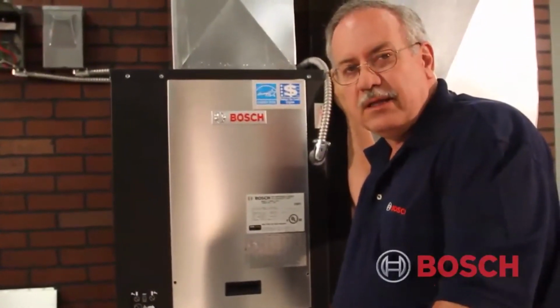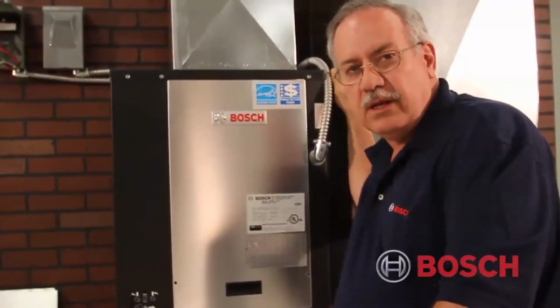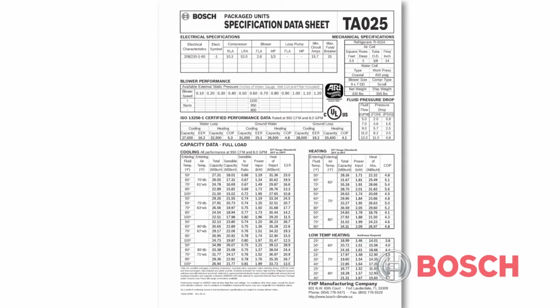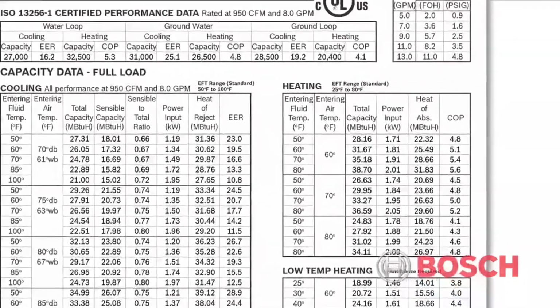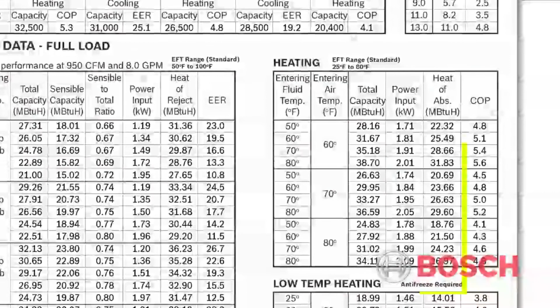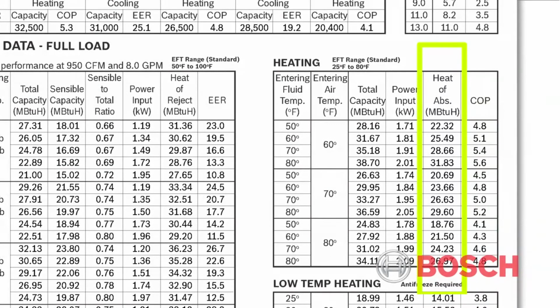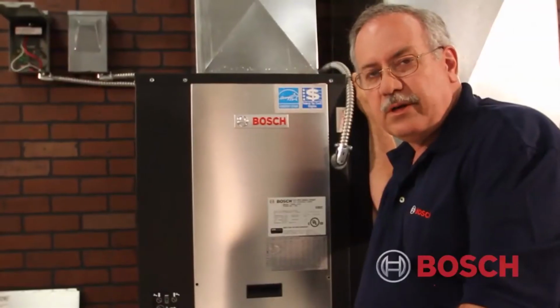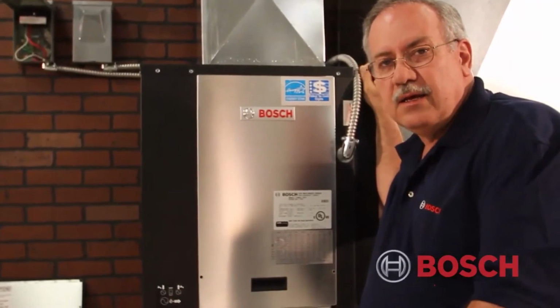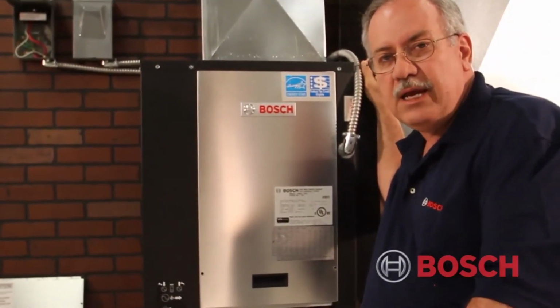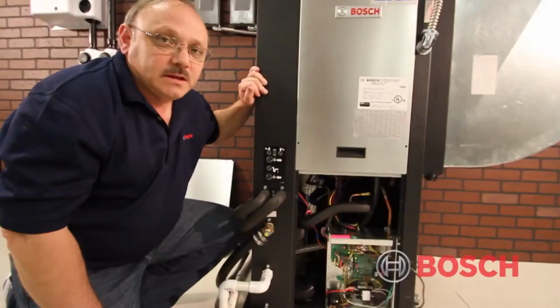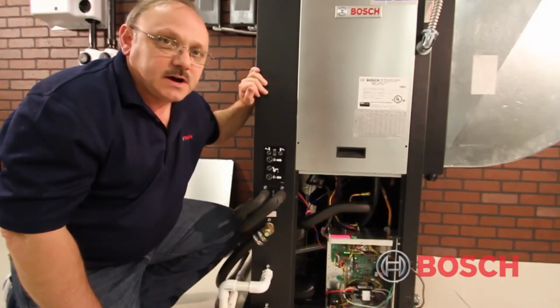Now, if I'm checking the system in the winter and I want to determine the other side, that would be referred to as heat of absorption. Some people call it heat of extraction. In that case, we're absorbing the heat from the earth into the fluid, transferring it into the refrigerant, rejecting the heat into the airstream. In this particular case, we'll be checking in cooling, therefore we're determining heat of rejection. As mentioned earlier, we like to check the water side diagnostics in the second stage of operation.